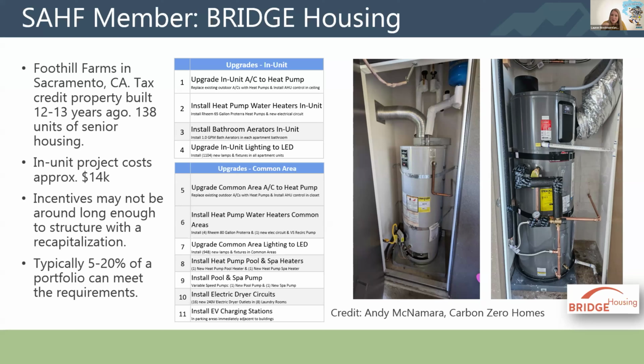In the end, residents' utility allowances increased slightly, even though heat pump hot water heaters are much more efficient, so they probably weren't going to use their full utility allowance anyway. Because of the dramatic increase in efficiency and the removal of gas systems, the affordable houser actually saved more than the utility allowances went up, so the NOI for the property was positive in the owner's calculations. What we've seen as we've looked at the data afterward is that things are running pretty true to what was in the model.